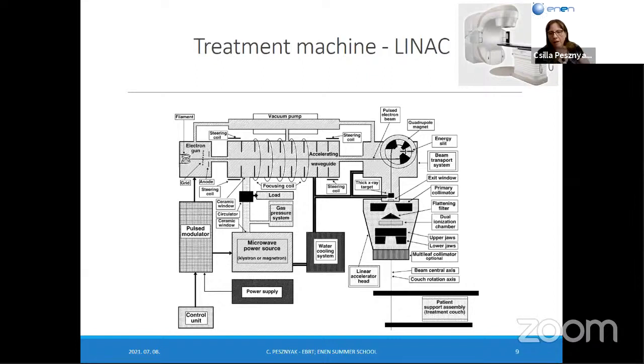inner and outer. And when we receive the beam, here is a pulsed electron beam. We have a bending magnet to change the beam direction. And here you can see the target where we receive the Bremsstrahlung X-ray. And here is the exit window and the collimator system, where we have primary collimators and secondary collimators, and here is a flattening filter. With the flattening filter, we can change the shape of the profiles. I'm going to show you in the next picture how it looks when we move out the flattening filter.